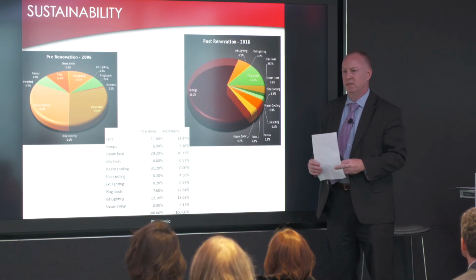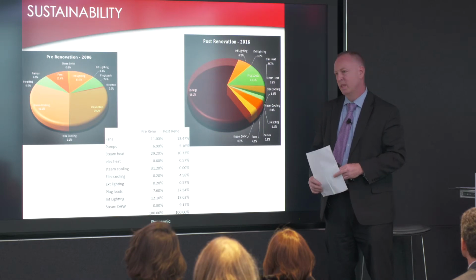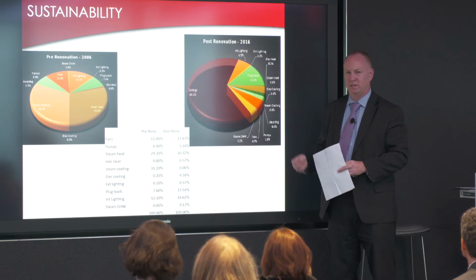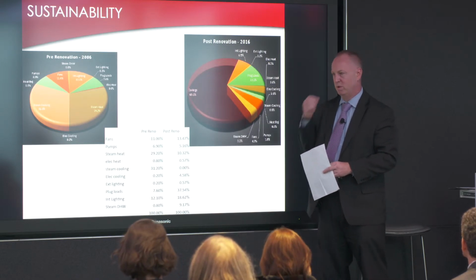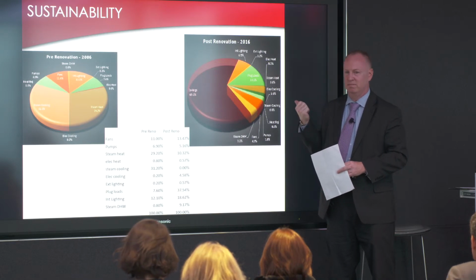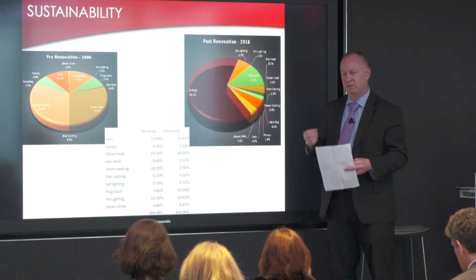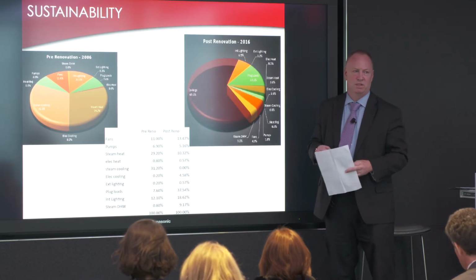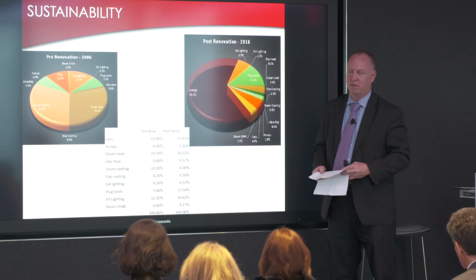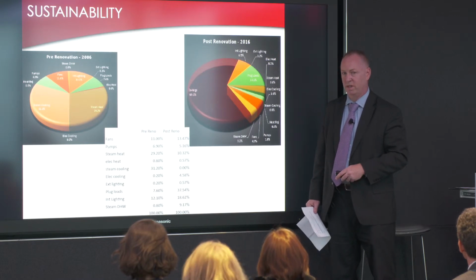So we're still, as Michael said, we handed and tossed the keys to the facilities staff about a month ago. And we're still on site, kind of going through, kicking the tires, making sure all the BMS sequences work, making sure that the demand ventilation, the active blinds, everything is in sync. Until you really work the building and go through something like the General Assembly, you need to see it in operation when it's in full swing to know what's working, what's not, and what has to get tweaked. So we're having that kind of fun now.